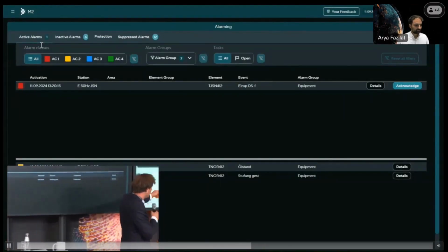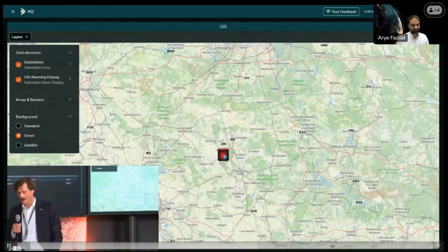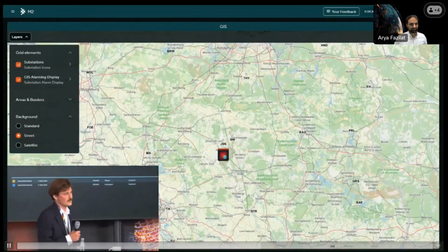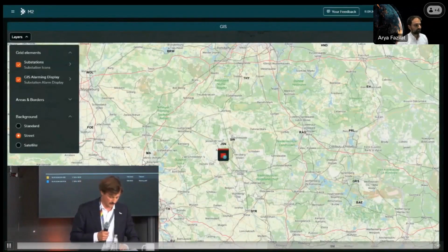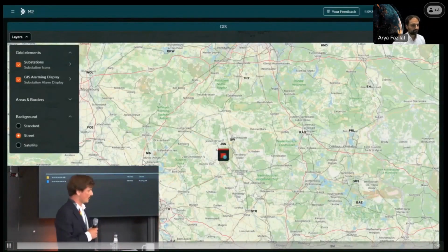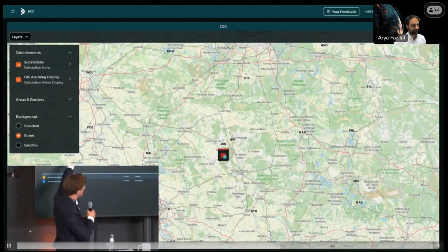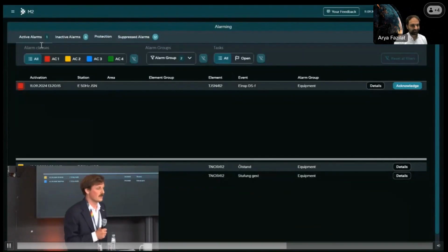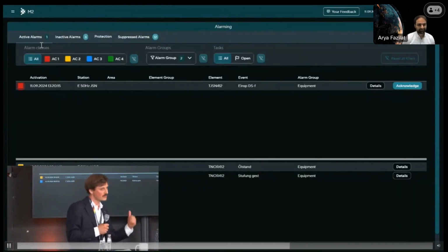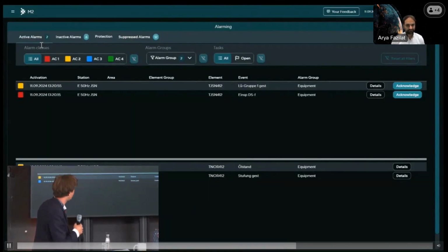And as you can see, for the ones that paid attention, also here, something appeared right now. This provides additional locational information about the alarms, to know exactly where something important is ongoing. In our case, we seem to have a threatening equipment failure on our transformer 412 in the beloved substation Jessen Nord. Don't worry, these messages are generated on IEC gateway level, so they do appear as actual alarms here in the system, but the real-world assets are actually okay.